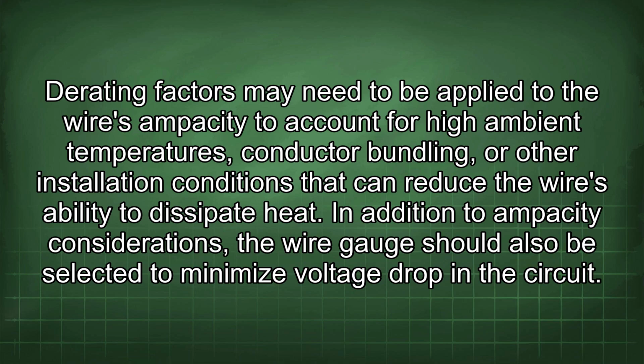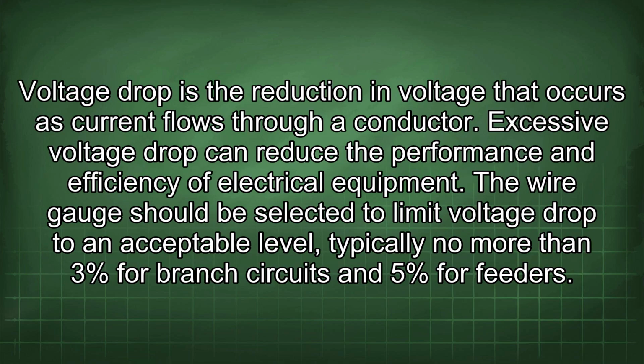In addition to ampacity considerations, the wire gauge should also be selected to minimize voltage drop in the circuit. Voltage drop is the reduction in voltage that occurs as current flows through a conductor. Excessive voltage drop can reduce the performance and efficiency of electrical equipment. The wire gauge should be selected to limit voltage drop to an acceptable level, typically no more than 3% for branch circuits and 5% for feeders.